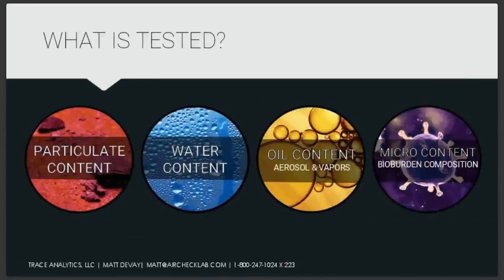So what do we commonly test? Well, particulate content, water content, oil content, both aerosols and vapors, and bioburden or microbial content. You may also need to check your purity for composition, as mentioned before, for CO2 or nitrogen if you use those kind of applications.